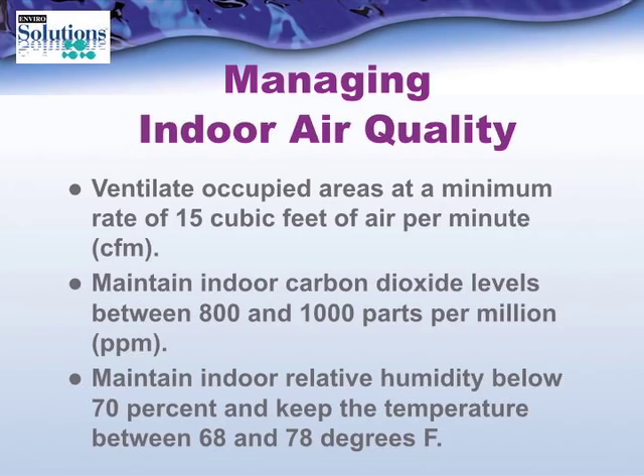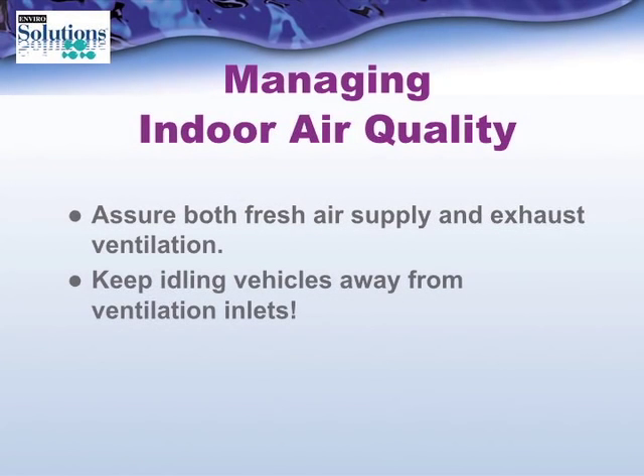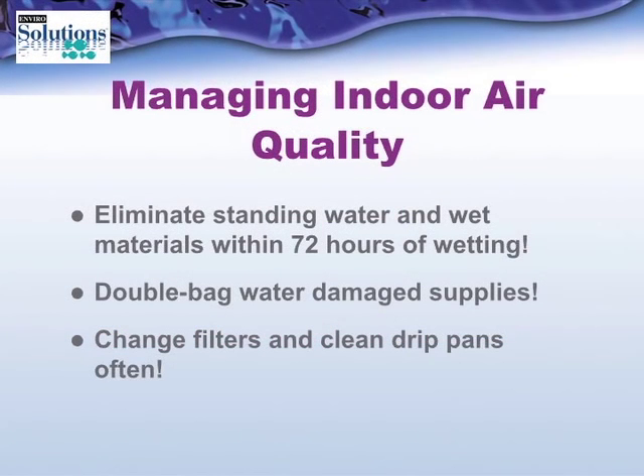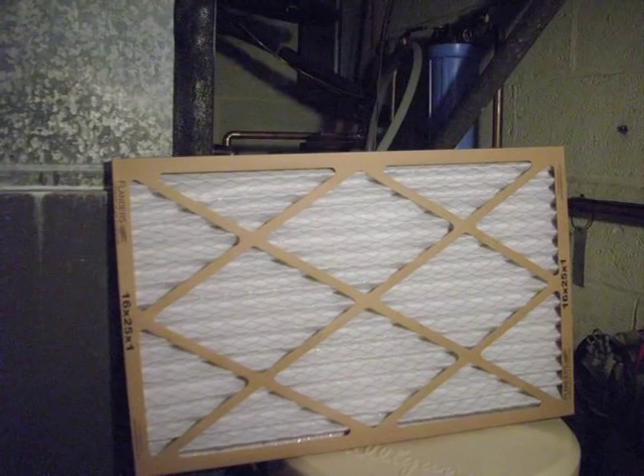We need to ventilate occupied areas at a minimum rate of 15 cubic feet of air per minute. We need to maintain indoor carbon dioxide levels between 800 and 1,000 parts per million, and maintain indoor relative humidity below 70% and temperature between 68 and 78 degrees Fahrenheit. Additionally, we need to assure both fresh air supply and exhaust ventilation, and keep idling vehicles away from the ventilation inlets. Eliminate standing water and wet materials within 72 hours of wetting, and double bag water-damaged materials and throw them out.